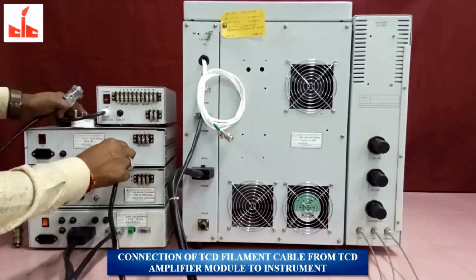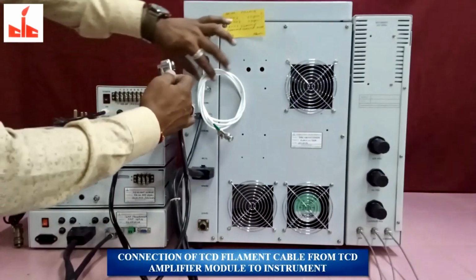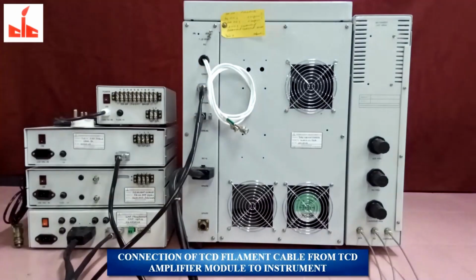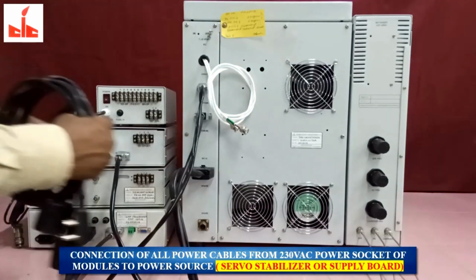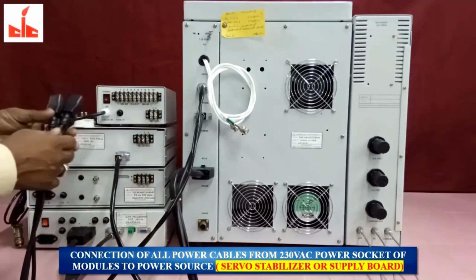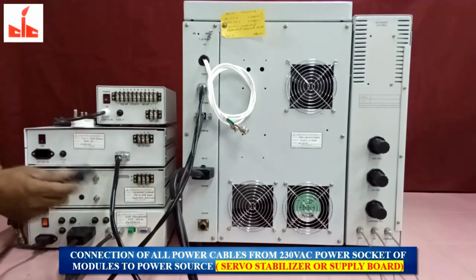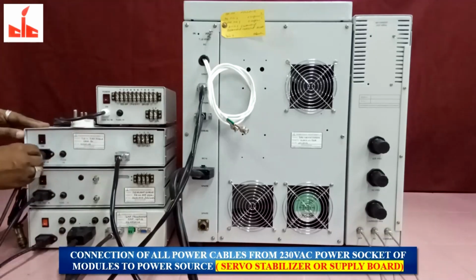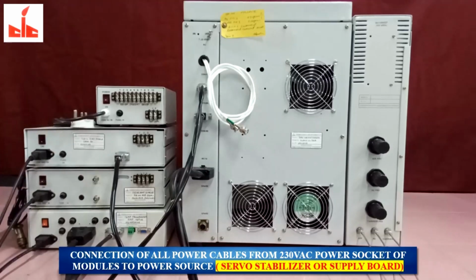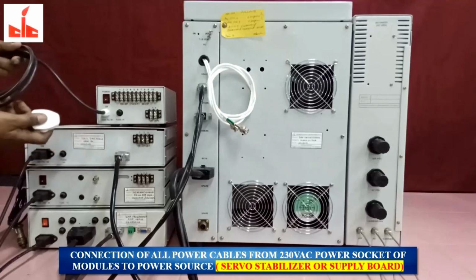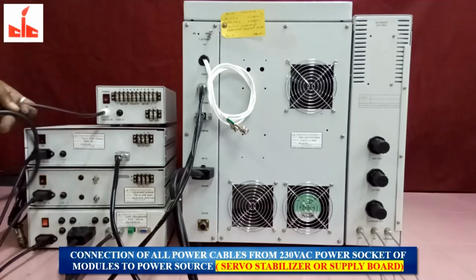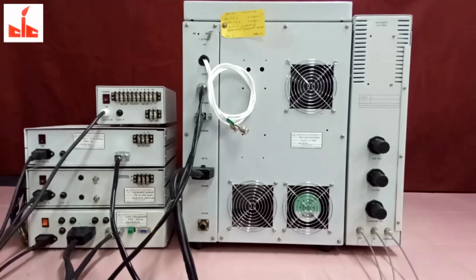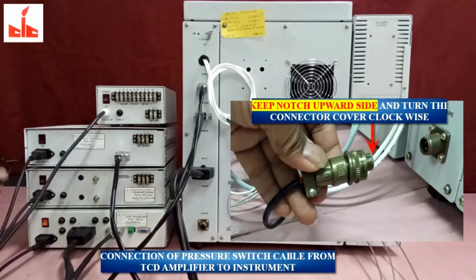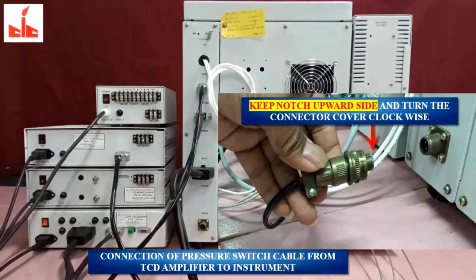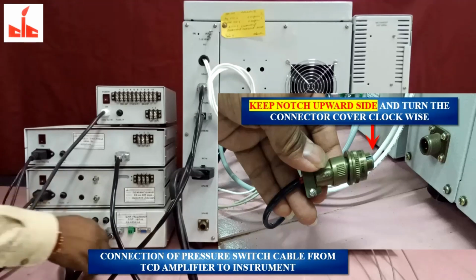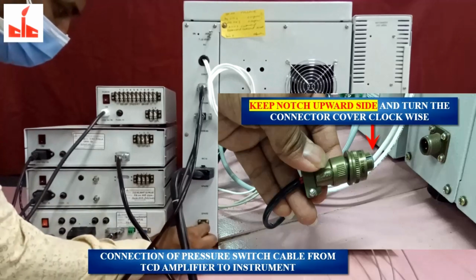Connection of TCD filament cable, from TCD amplifier module to instrument. Connection of all power cables, from 230 volt AC power socket of modules, to power source, servo stabilizer or supply board. Connection of pressure switch cable, from TCD amplifier to instrument. Keep notch upward side, and turn the connector cover clockwise.